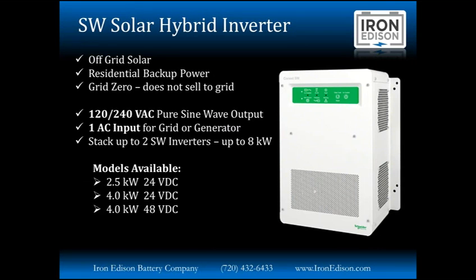This is a great inverter for off-grid solar applications or just doing a battery backup in a residential grid-tied application. The SW inverter is a grid zero inverter, meaning it does have an AC input, but it does not have the ability to sell energy back to the grid. It comes as a 120/240 volts pure sine wave output. Again, a single AC input.